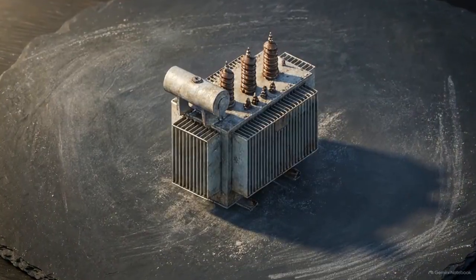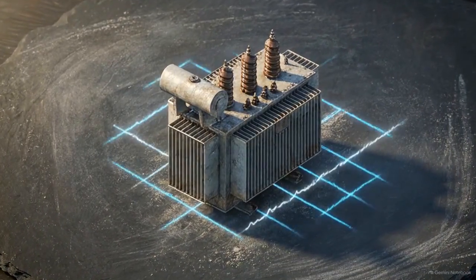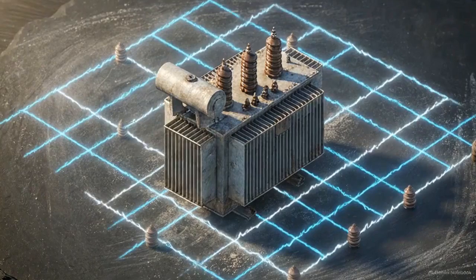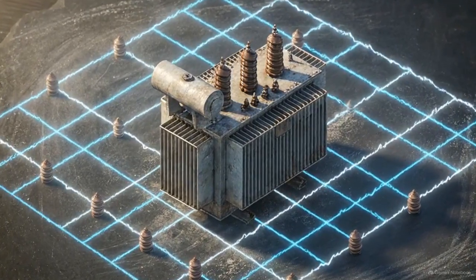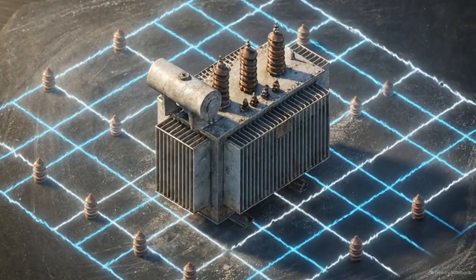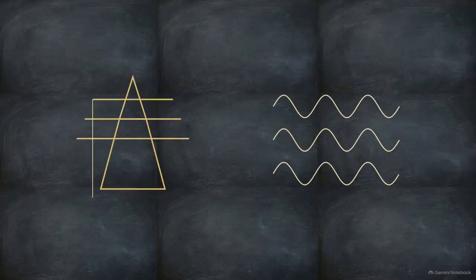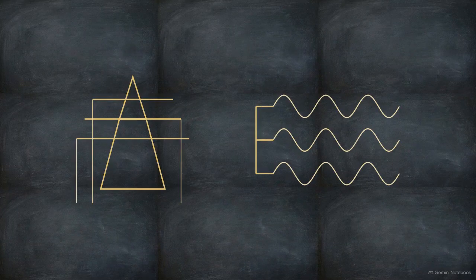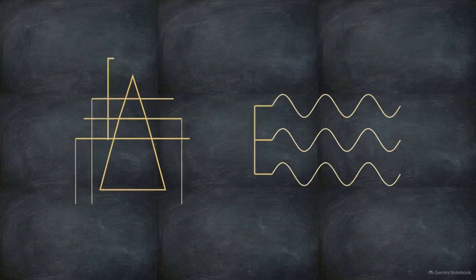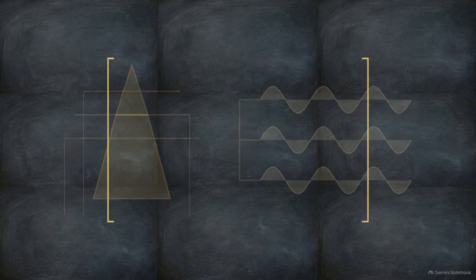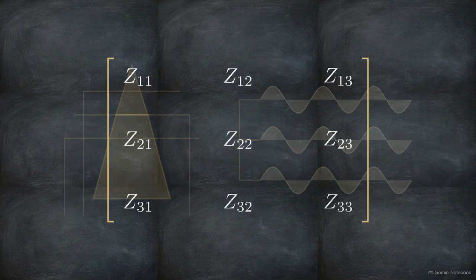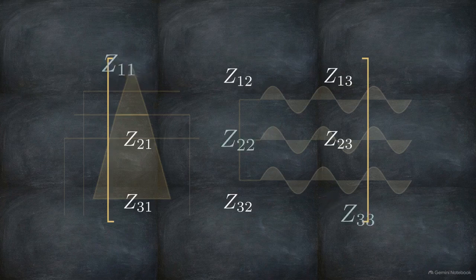Changing our basis from physical phase space to mathematical sequence space allows engineers to treat a highly erratic unbalance as a superposition of perfectly symmetrical states. Grid equipment, like overhead lines and generator windings, is defined by its impedance. In a three-phase system, this is represented by an impedance matrix. Look at this 3x3 physical impedance matrix.